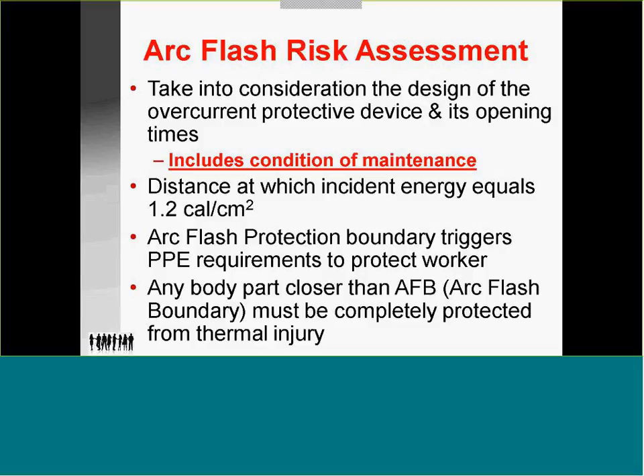Takes into consideration the design of the overcurrent device and its opening time. Includes condition of maintenance now. This is an add-on. If you don't maintain the equipment, it will not protect us. With incident energy equals 1.2. This is usually measured at 18 inches from the source. The arc flash boundary triggers PPE requirements to protect the worker.